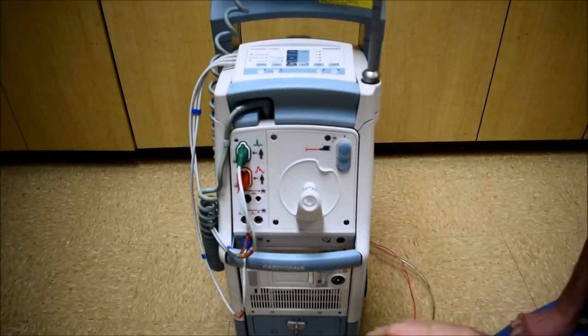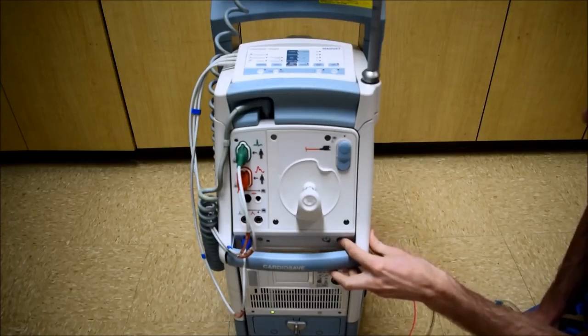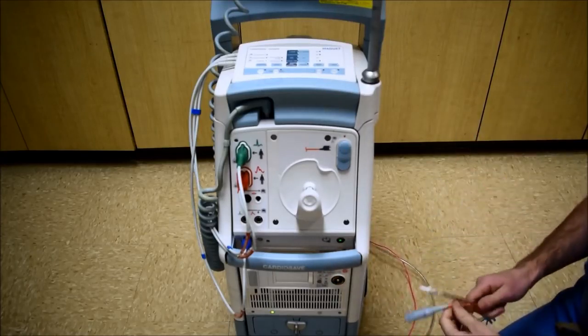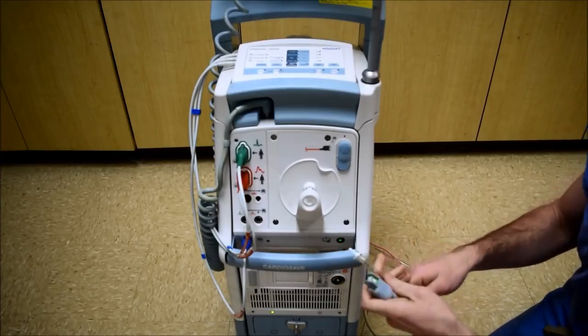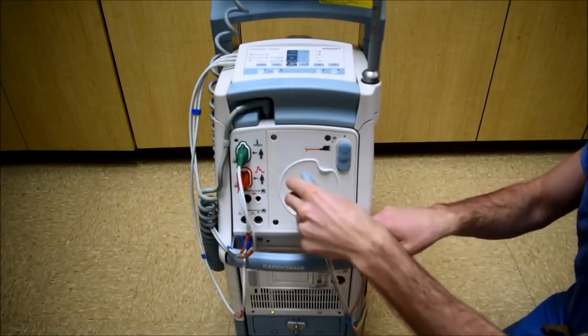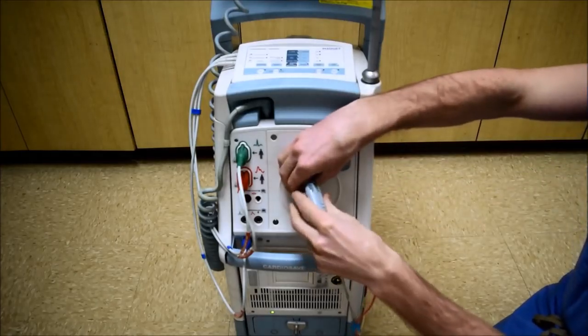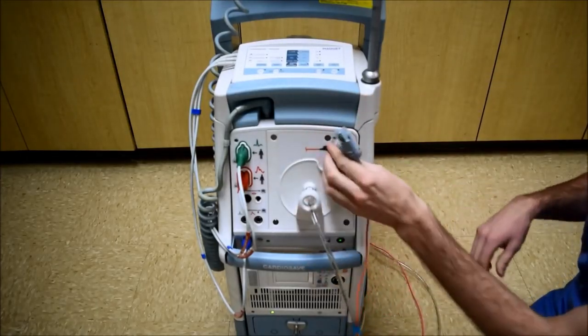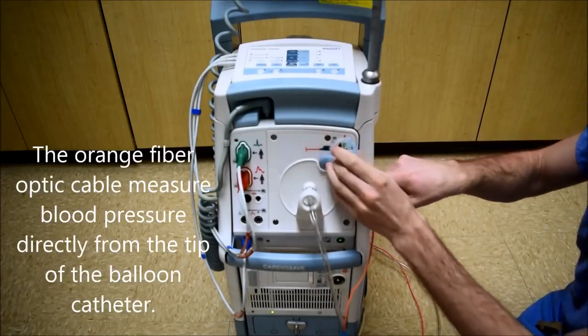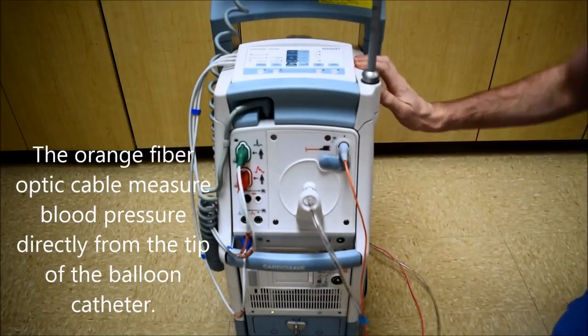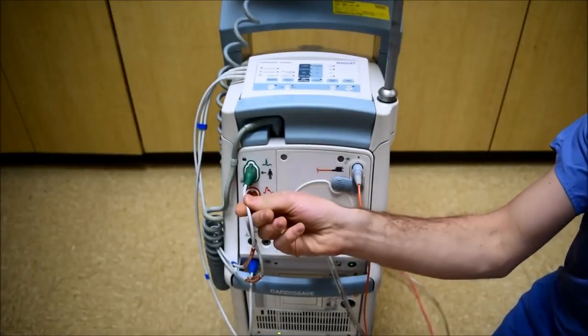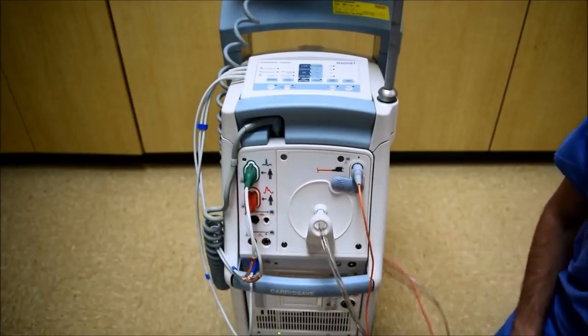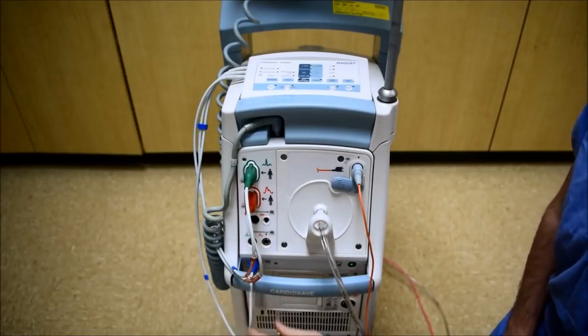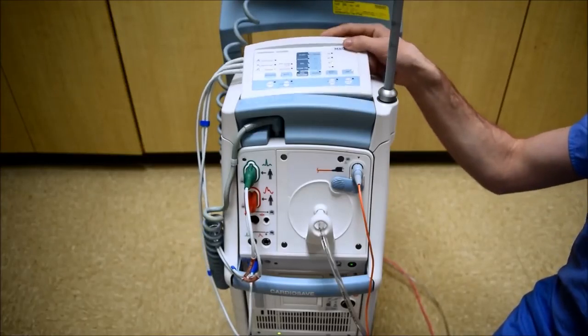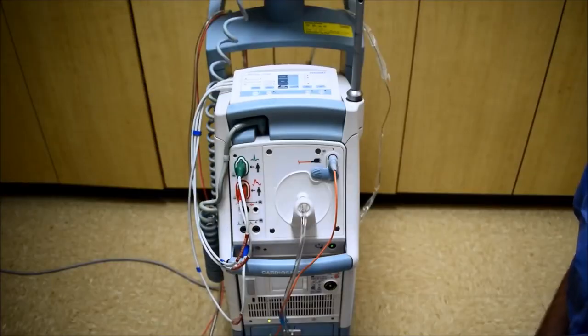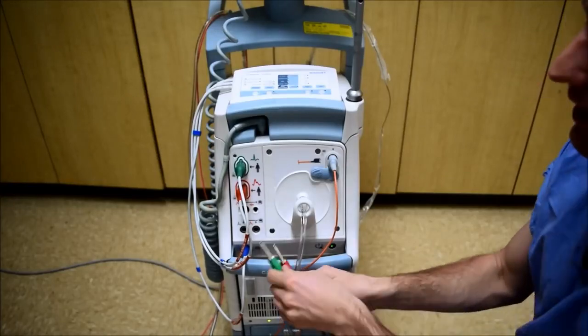Okay, let's get started. To power on the balloon pump, press this button here. And when you receive the lines from the sterile field, they're inserted here. This line is where helium is shuttled back and forth, and this is the fiber optic cable. The EKG line and pressure monitoring lines are connected here. This blue line is only for the purpose of this video, as it goes to the simulator. If you're slaving from the patient's monitor, those lines are hooked up down here.